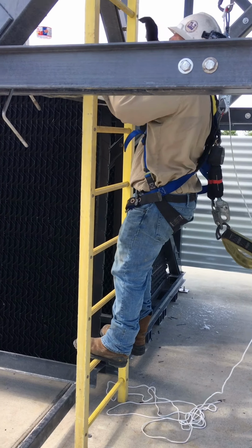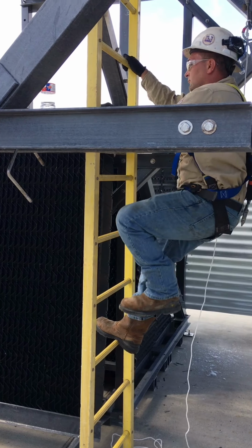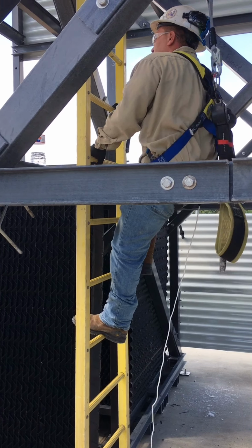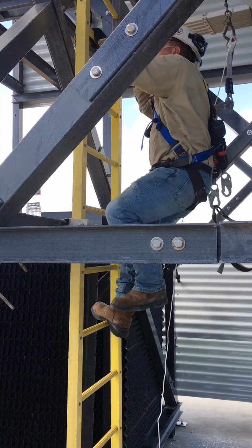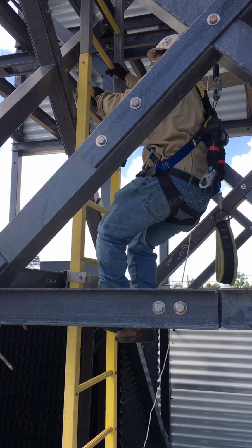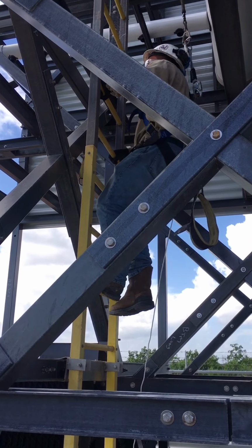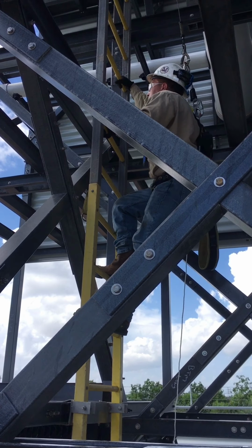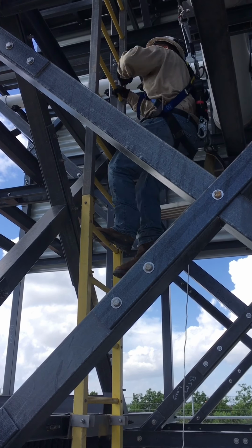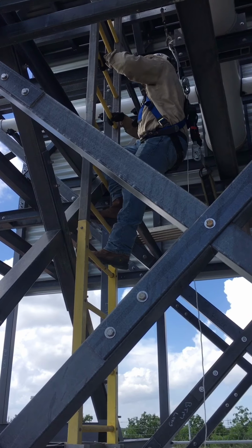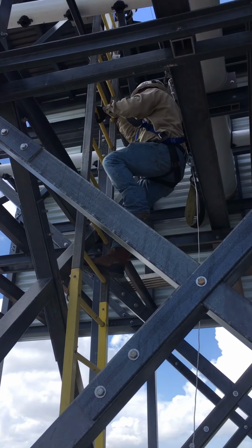You will attach a rope to the vertical self-retracting lifeline so that the lifeline may be retrieved from the bottom of the ladder. When using a vertical self-retracting lifeline, you will first pull the lifeline swiftly to ensure the lifeline locks and is performing correctly. You will then use the rope to pull the vertical self-retracting lifeline down to be attached to your harness.